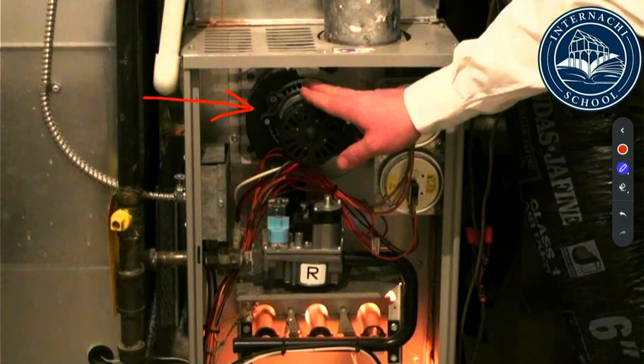But you should be able to recognize the inducer fan. Once the thermostat calls for heat, the computer that's inside here is going to do a quick check. And Lorain, Ohio, thank you. It's going to do a quick check, just to make sure that everything's connected and everybody's communicating with each other. The first thing that we're going to see is this inducer fan start spinning. The computer doesn't know if the fan blades are broken or there's a bird in there or the motor is shot. So there's no way to know that it's actually creating a draft, except for these guys over here.